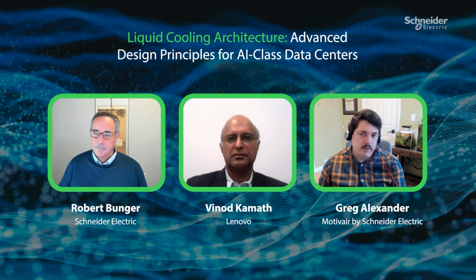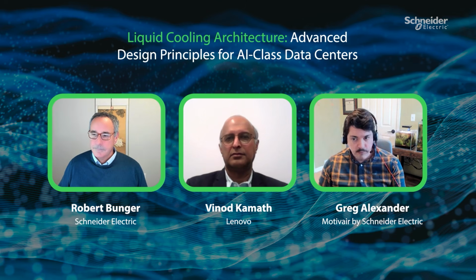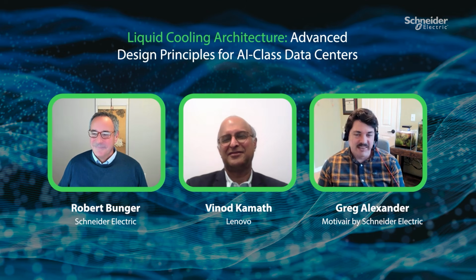So the CDU fits into this ecosystem as a barrier between what needs to be a very clean and controlled fluid going to the chips, and facility water, which historically might have been around for a long time. There's wrought iron pipes, there's a lot that can go on there that we don't want anywhere near the IT equipment. At the end of the day, I think barrier is the best description of what a CDU is.